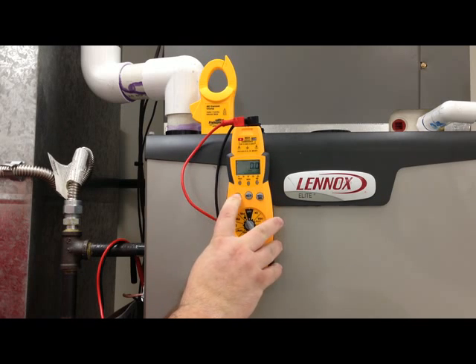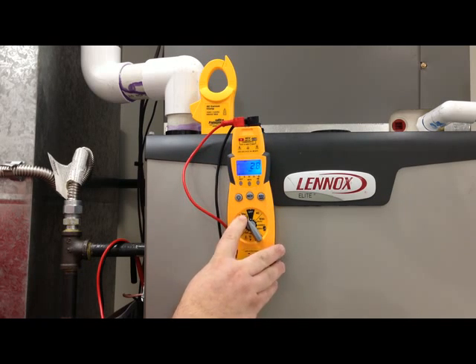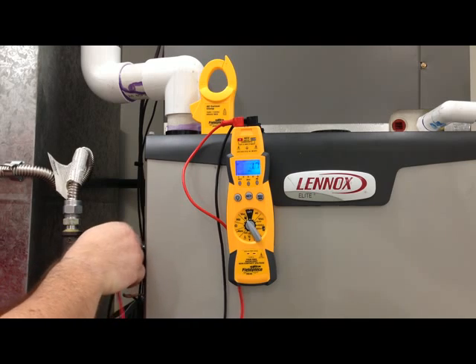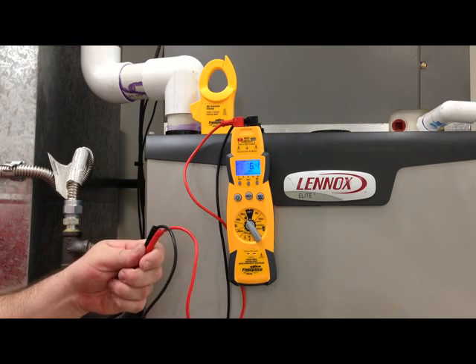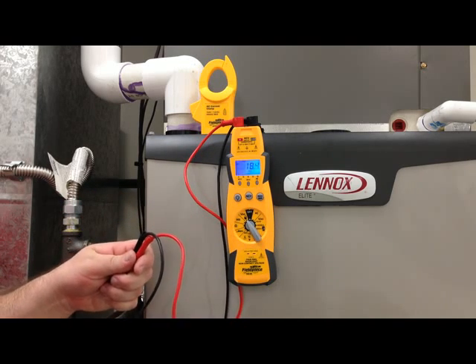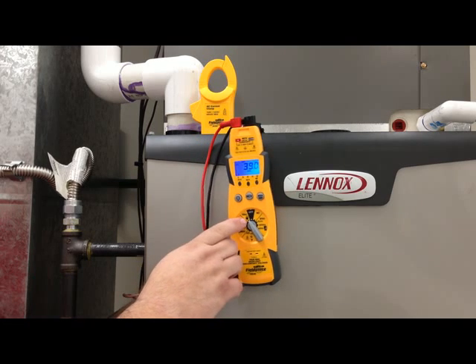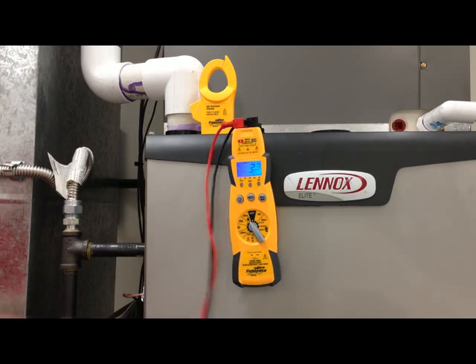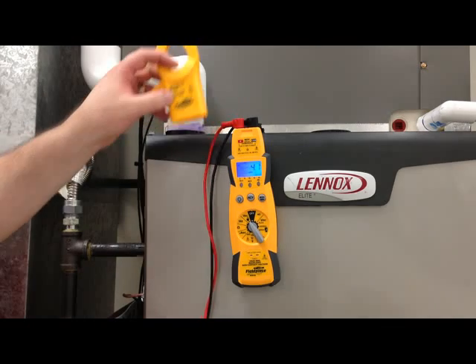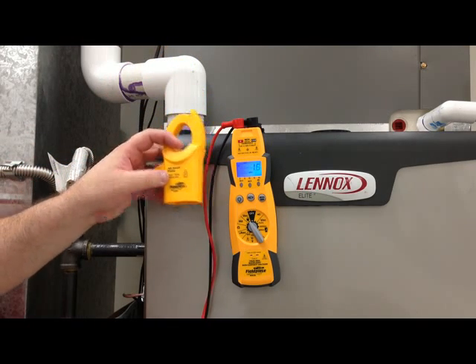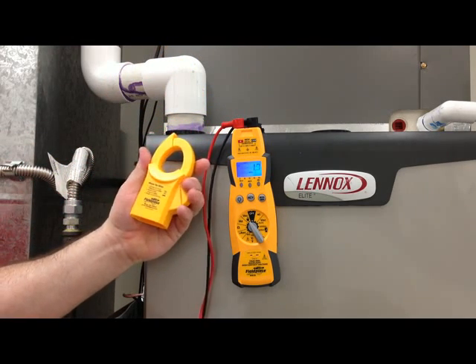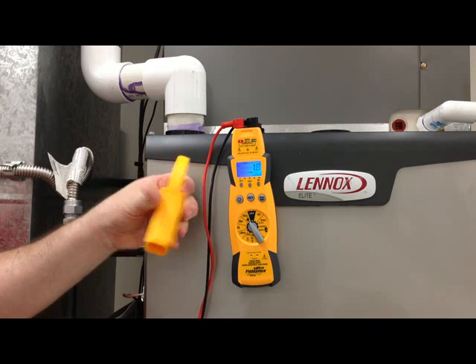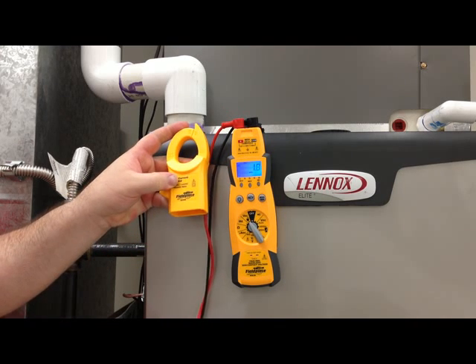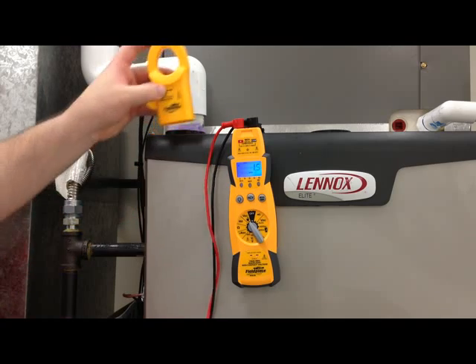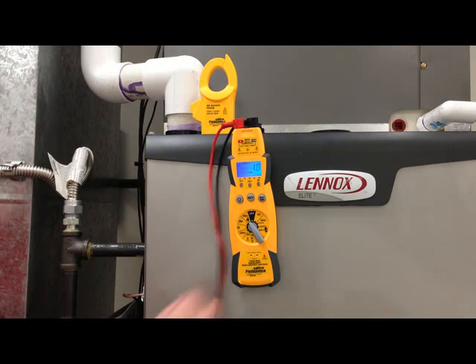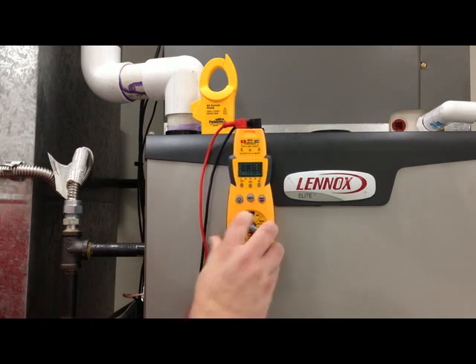The first one that I'm going to turn to here says volts AC. So if I were going to measure AC voltage, I could take my meter leads and actually measure the voltage of the circuit. But notice the image of the little jaws there. Being a Fieldpiece meter, this allows me to take the leads off the top of my meter and snap on the amp probe attachment or the amp clamp attachment and be able to measure the amperage of a circuit without breaking the wires. We can then turn onto the next dial.